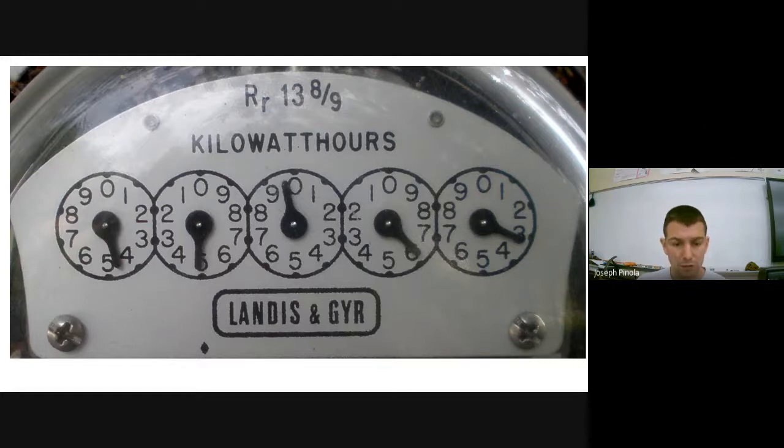You might notice, if you look closely at the dials, that they're flipped. The first dial on the left reads like a clock. It starts out 0, 1, 2, 3, 4, 5, all the way up to 9, and then back to 0. And so you would read it in the clockwise direction. The second dial is flipped. It goes the other way. That's due to the inner mechanisms of the device. You would read this dial backwards.